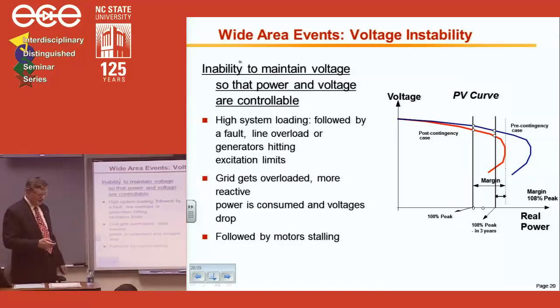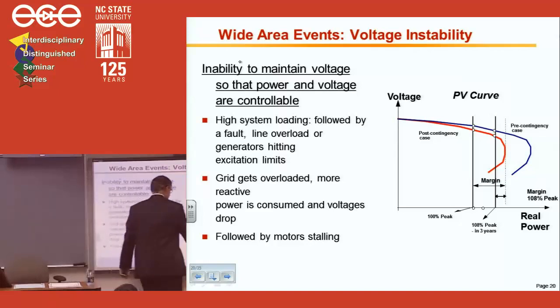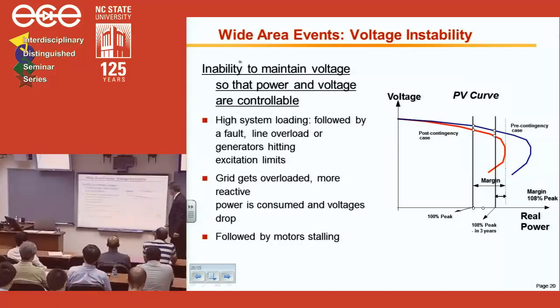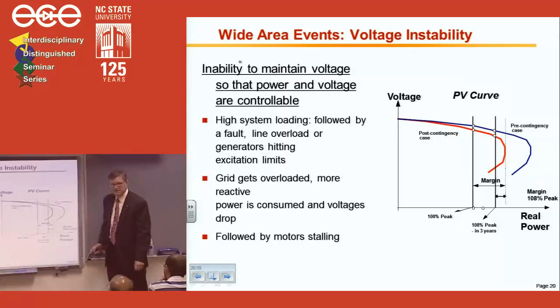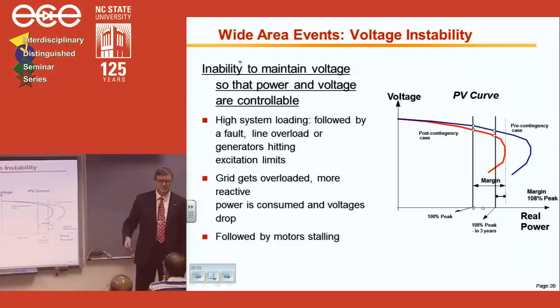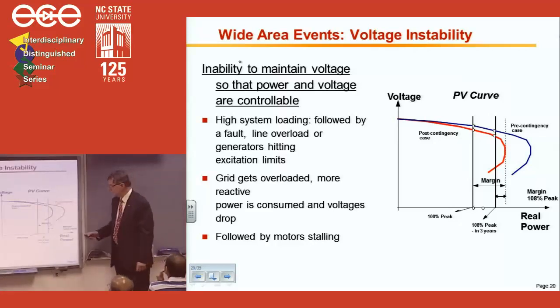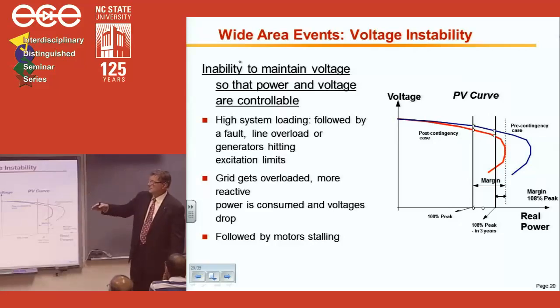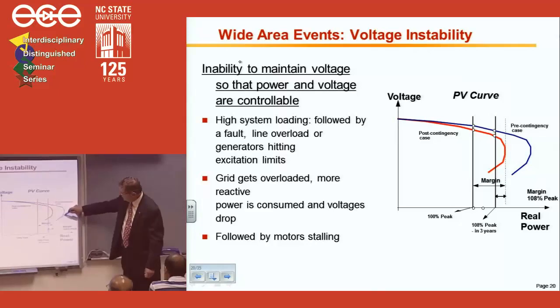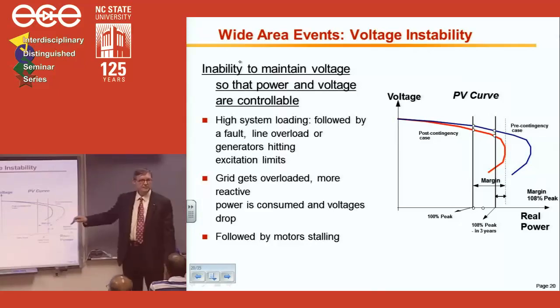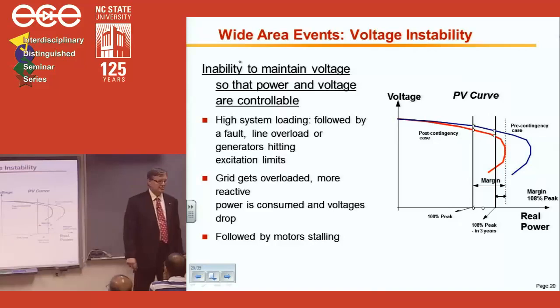So for voltage instability, I'll take a very simple approach. This is the famous PV curve, how voltage stability is usually described. If you have an inability to maintain voltage so that power and voltage are controllable, you are voltage unstable. Beyond the knee of the curve, you get into the instability region, and then into an outage, possibly a blackout.